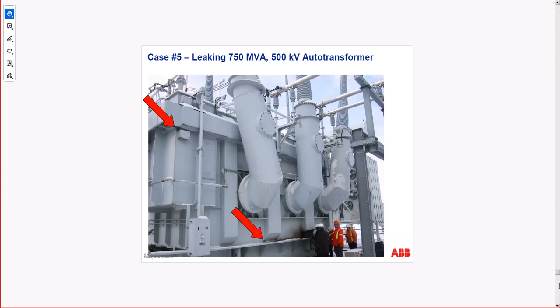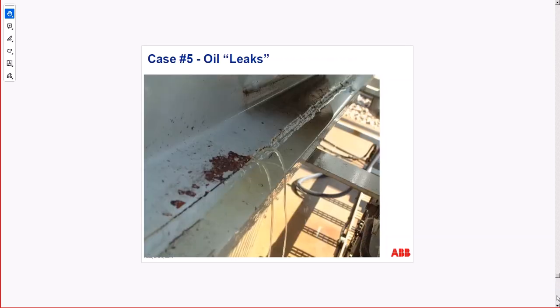We have leakage points in the tank. You see ASEA Brown Boveri transformer. It's called also Hitachi. Don't be confused. Everything that you see Hitachi, or 90% of what you see Hitachi transformers, breakers, and so on, is actually ABB. Well, this is what it is. It's called ABB in the background, but is having on top of a name, you know, Hitachi.